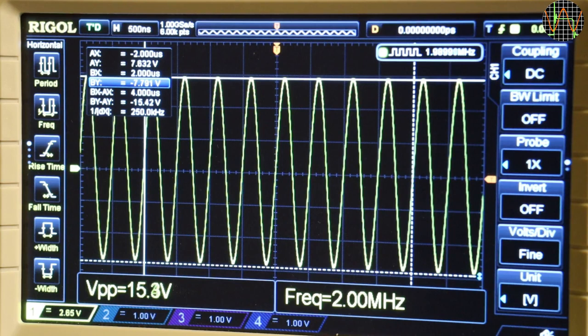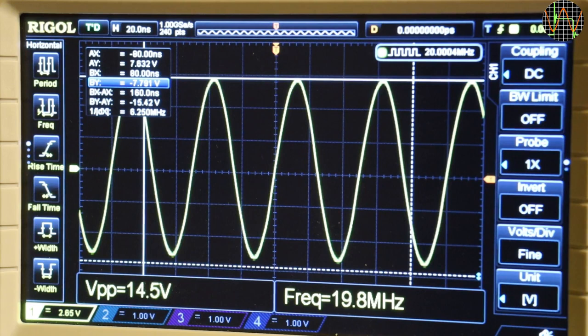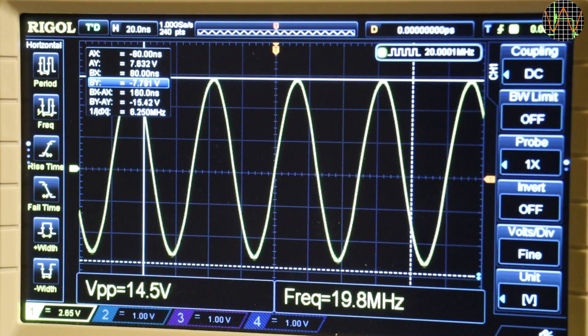Next, the procedure asks for 20MHz and the signal should not have changed by more than 15% like a drop to 5.1 divisions. A quick adjustment of the scope timebase and the voltage peak-to-peak has dropped from 15.2 to 14.5V peak-to-peak, which is about 4.6%. Visually, it still occupies about 5.8 divisions so again we are well within specs for flatness, but of course all this depends how flat the scope's frequency response itself is.